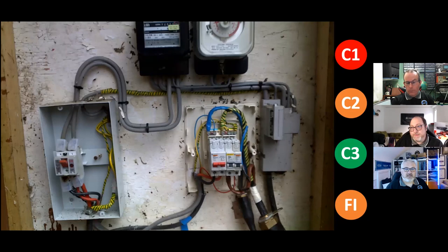And this was in the back of a house, in what was a converted old toilet block where someone had just battened it in. There was evidently a new supply put in there at some point, and this was the lash up that the builder had done. So this was not an electrician who did it, this was a builder who'd done it. And I believe they'd moved the fuse board to somewhere nice, and they also ran a supply out to a shed. But yeah, it's just a C1.